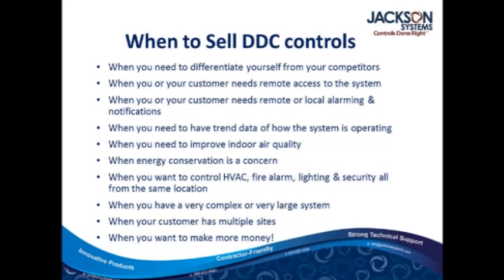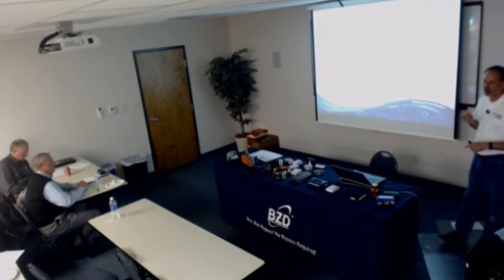If there's a need to tie your building's other functions together, HVAC, fire alarms, lighting, security, all from the same location, and this is becoming a really big deal. You can have your card access system that unlocks your doors if you wanted to. The president of the company can come in and swipe his card, and as he swipes his card to unlock the door, it turns on the hallway lights to his office, and it turns on his office lights, and it turns on the VAV box to his office, and the whole building just kind of comes to life just because the control system in the building knows that he swiped his card at the door, so he's in the building. If you set it up to swipe it on the way out, everything can go back off automatically.